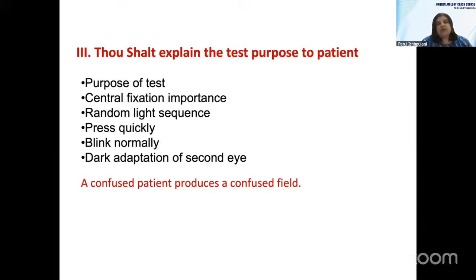Second, you should maintain standardized testing conditions. The light should be kept off when the machine is getting booted up. Boot up calibration depends upon the ambient light. If the light is on when the machine is getting started, it will alter the contrast and your output will be different. If you compare a visual field calibrated with the light on against one calibrated with the light off, the outcome is going to be very different. Remember that perimetry measures contrast and not just brightness.